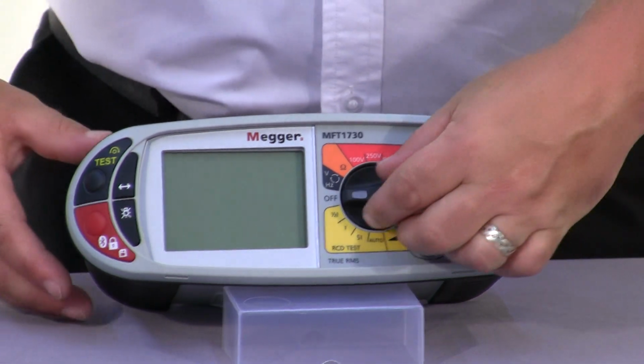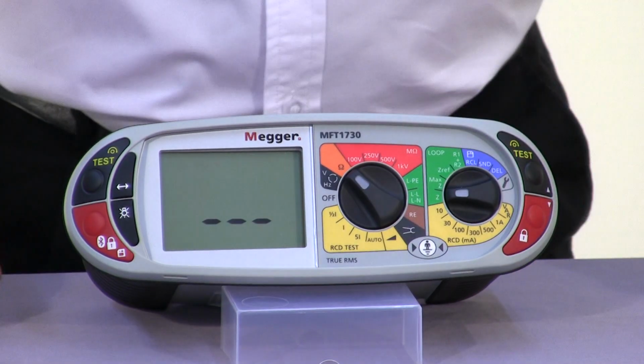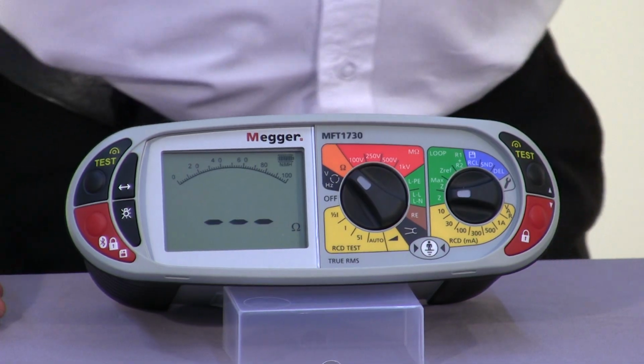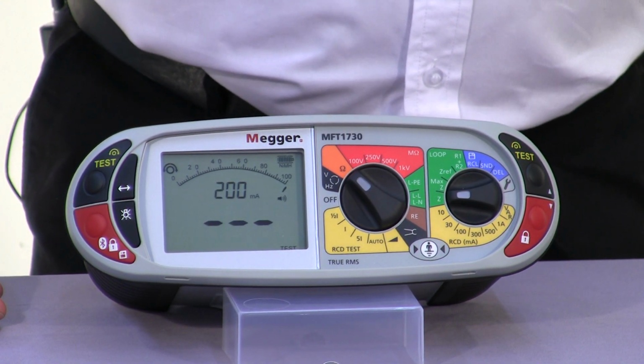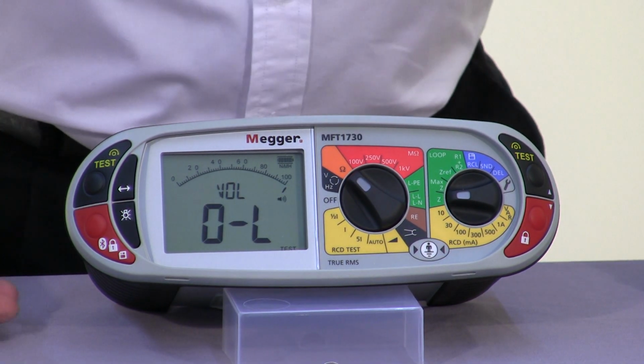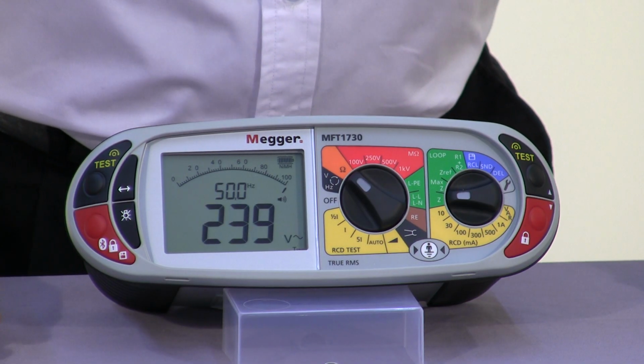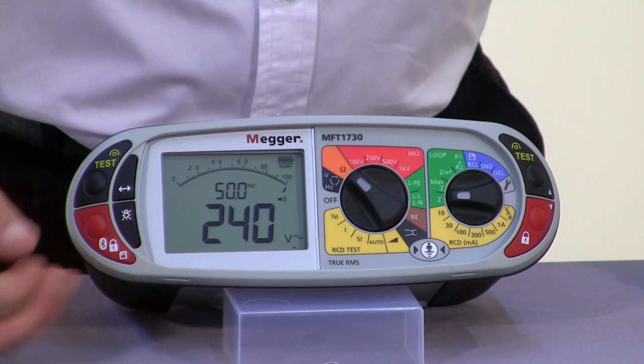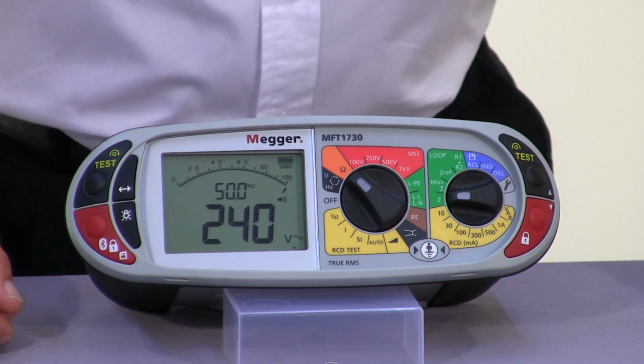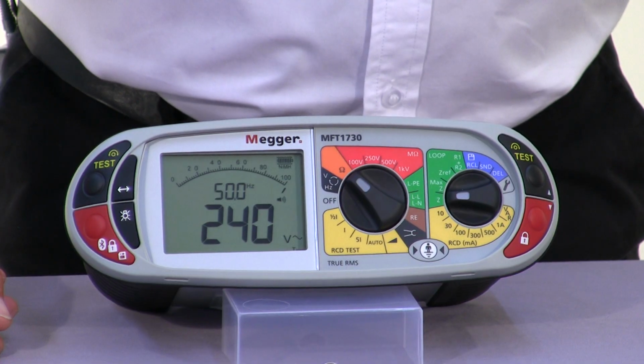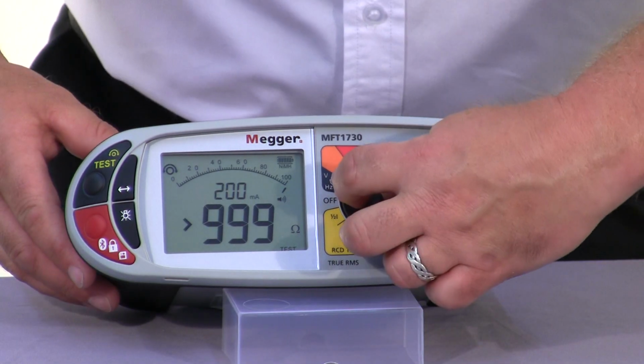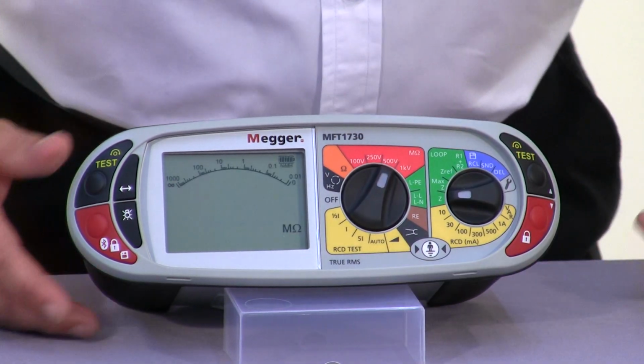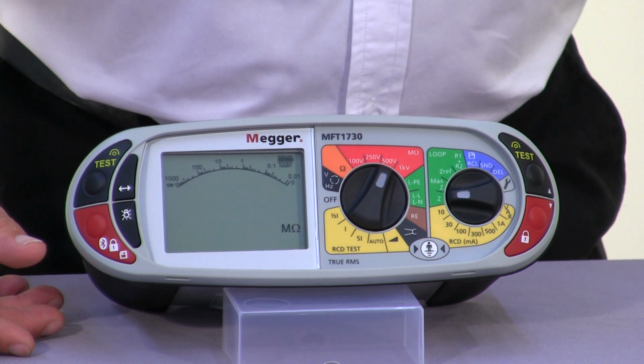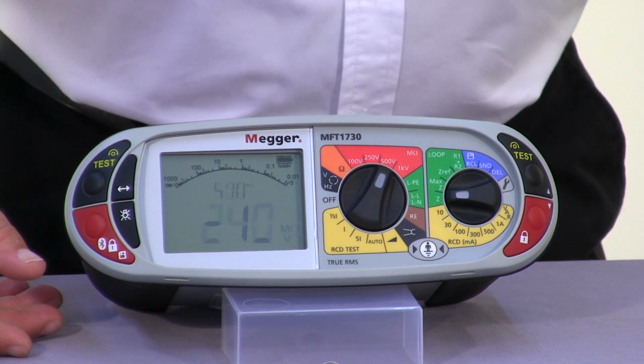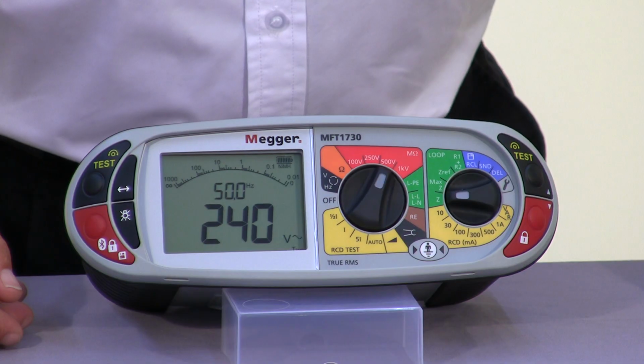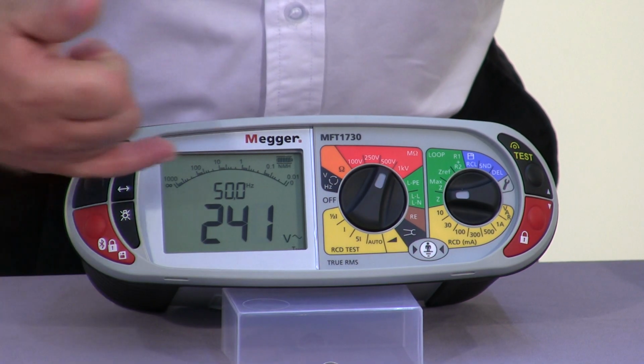So if, for example, we were selecting one of our dead tests, whether it be continuity or insulation test, and we accidentally apply a voltage, you'll see straight away we get an indication on the screen, you get an audible indication, and then the unit will click over and actually indicate the voltage that you've attached the probes to. This is exactly the same when you're carrying out an insulation test.